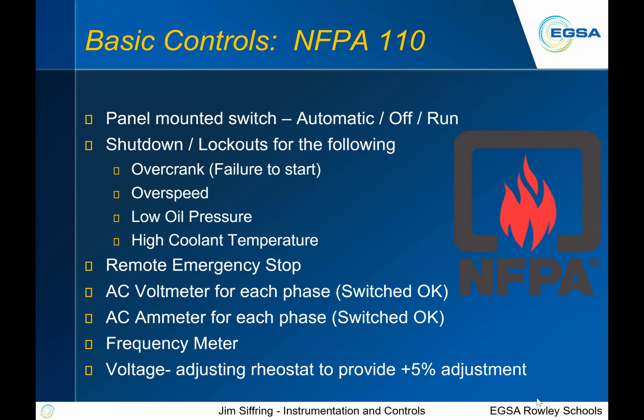Well, the first thing we have to have is a panel mounted switch. It's got to have 3 positions: an automatic position, an off position, and a run position. That's a minimum. It's got to have shutdowns or lockouts for all of the following 4 items: overcrank, which is failure to start, overspeed, low oil pressure, and high coolant temperature. You need to have some sort of a remote emergency stop button. You need to have an AC voltmeter for each phase. You can switch between them if you want. That's fine. Same with the AC ammeter for each phase. You have to have a frequency meter, and some kind of voltage adjusting rheostat to provide a plus or minus 5% adjustment from nominal.